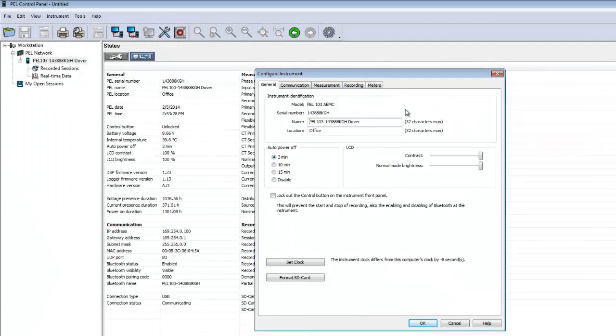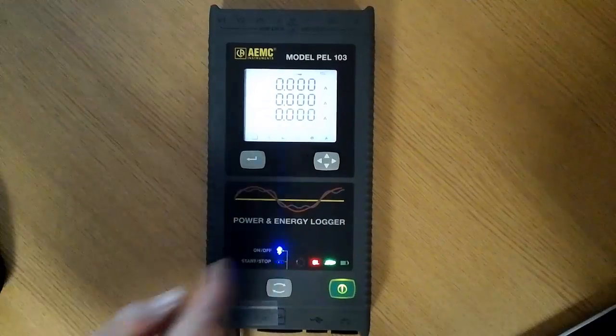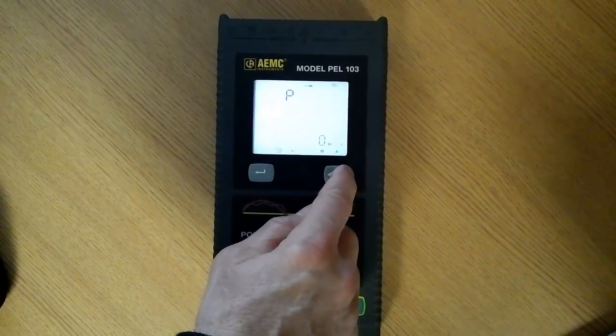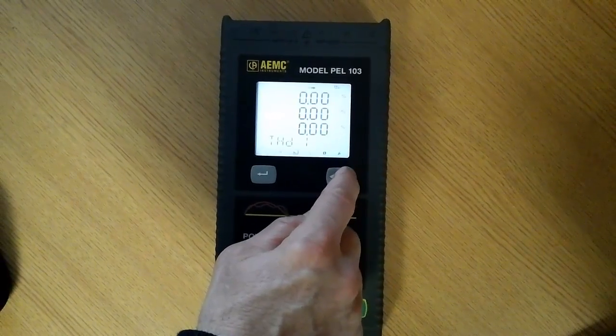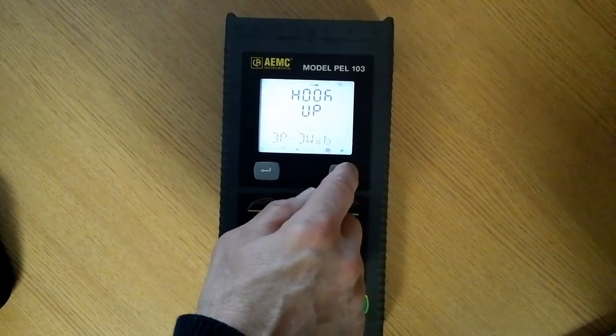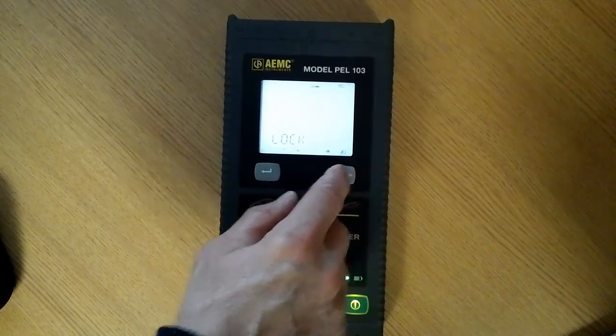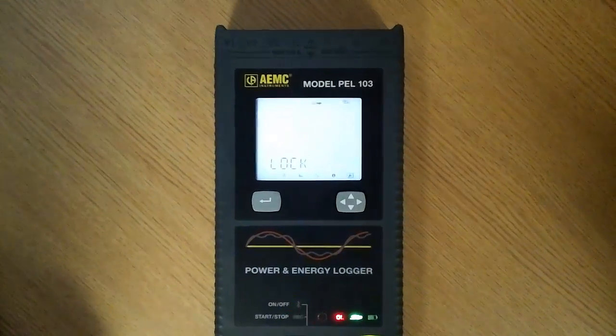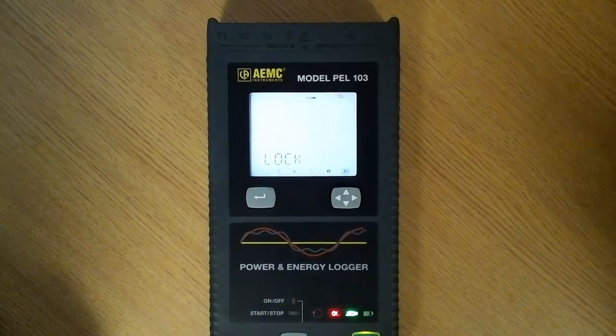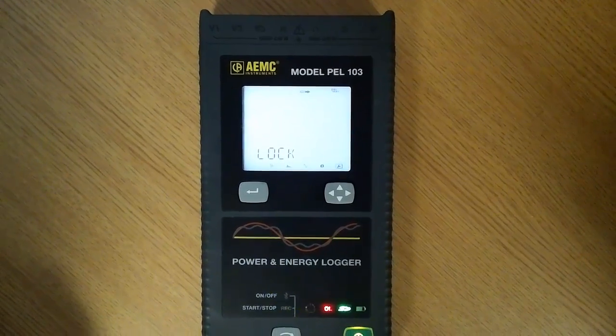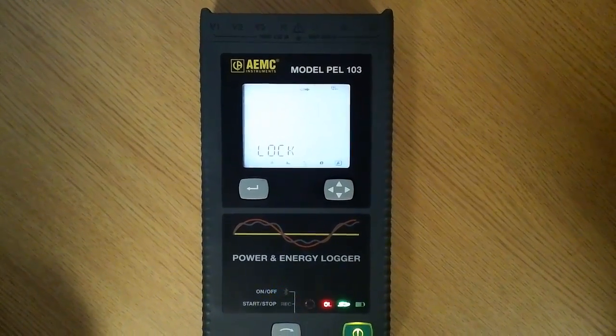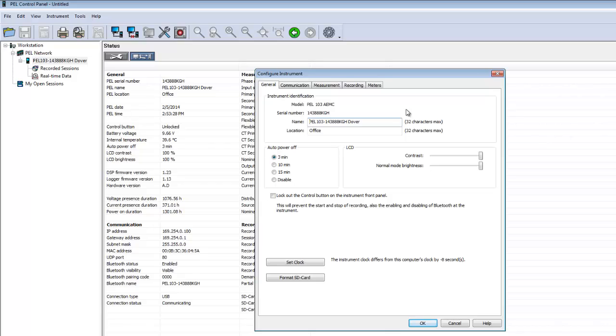Note that when the Configure Instrument dialog box is open, Configuration Mode on the PEL's LCD display screen is disabled. If you attempt to configure through the display at this time, the word Lock appears, and all configuration options are inactive. This prevents configuration conflicts caused by two users simultaneously attempting to configure the PEL, one through the PC and the other through the instrument itself.